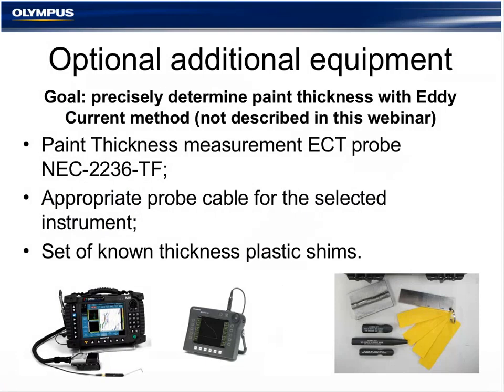As optional additional equipment, Olympus happily supplies paint thickness measurement probes, the NEC 2236 model, that can work with the Nortec 500 or the OmniScan eddy current array or eddy current testing module. The same OmniScan can do conventional eddy current and eddy current array, as seen in the picture below, with a proper cable, of course, and a set of thickness plastic shims. It's outside the goal of this presentation to explain this method of measuring paint thickness, but Olympus can happily supply you with more information if you type those in the Q&A of this webinar.